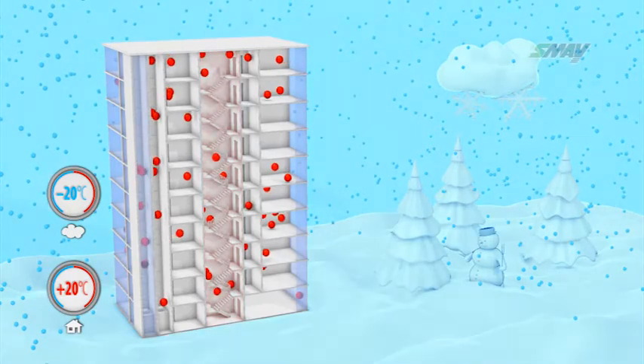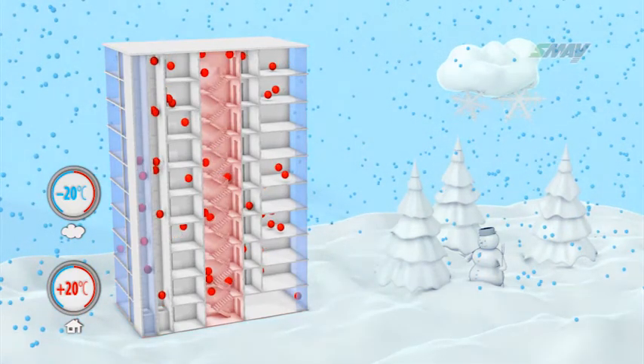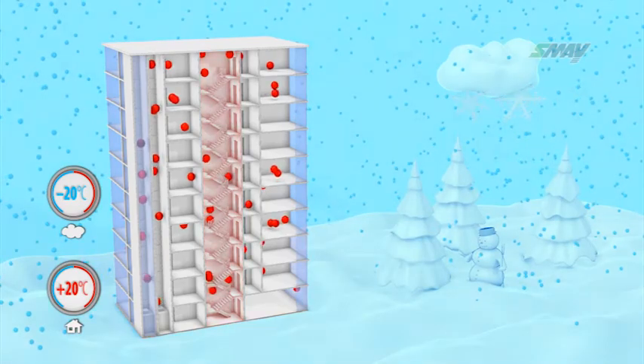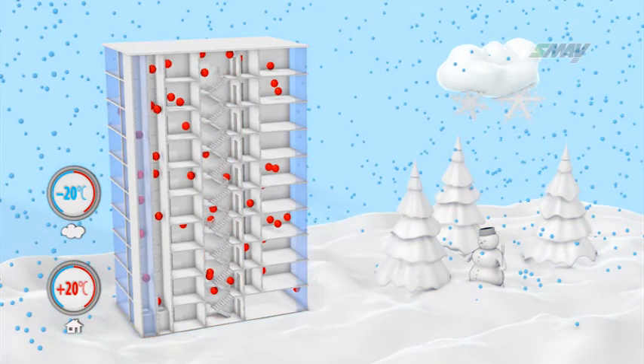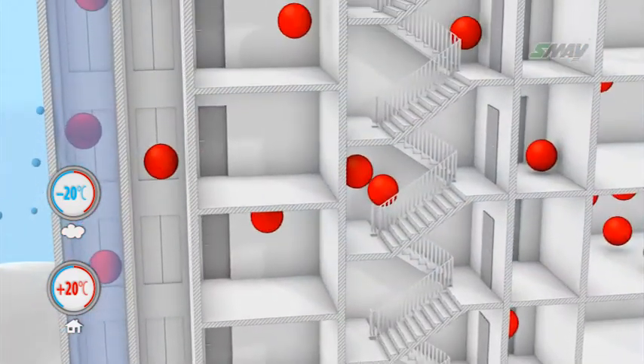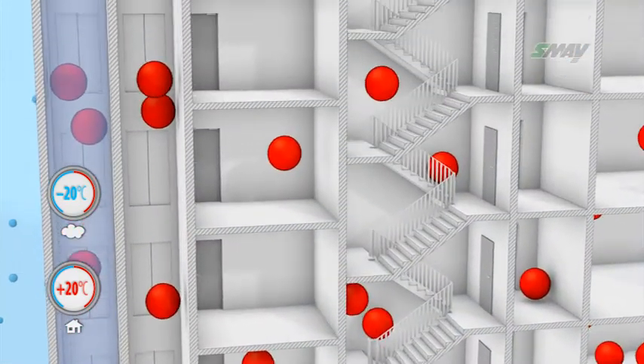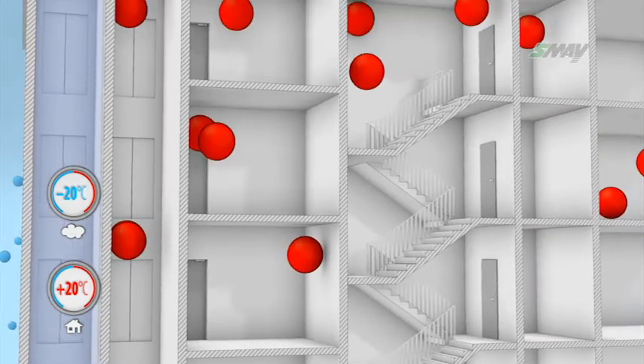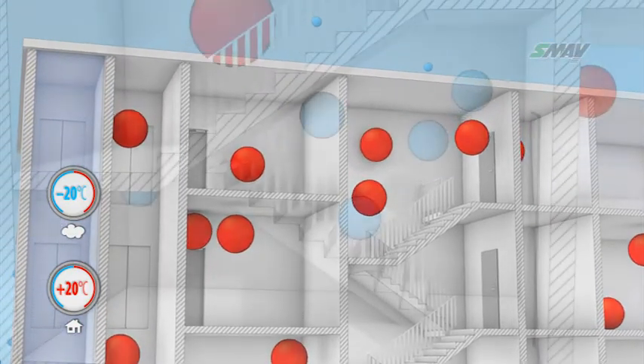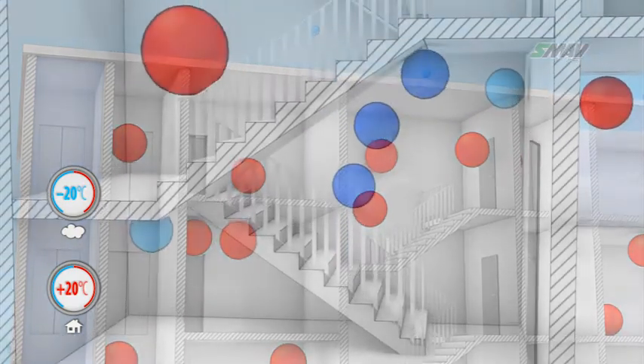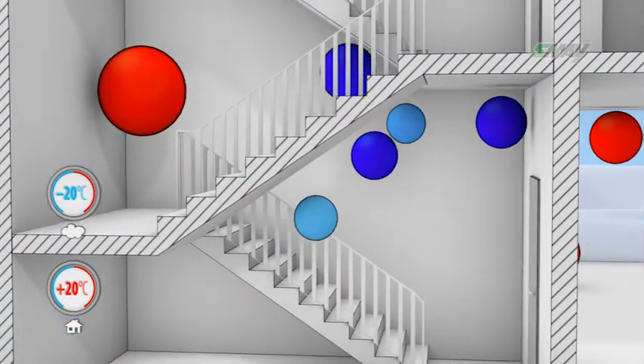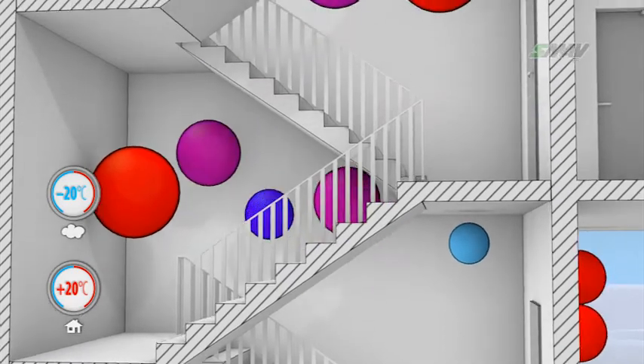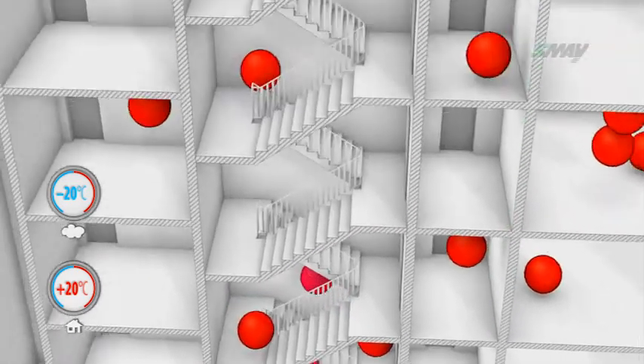If the stairwell is located in the interior of the building and not connected with the atmosphere, the stack effect will occur immediately once pressurization begins, if the air supplied is of a different temperature than the air inside the stairwell. Due to the significant heat capacity of the stairwell structure, even long-term pressurization will not eliminate the occurrence of the stack effect.